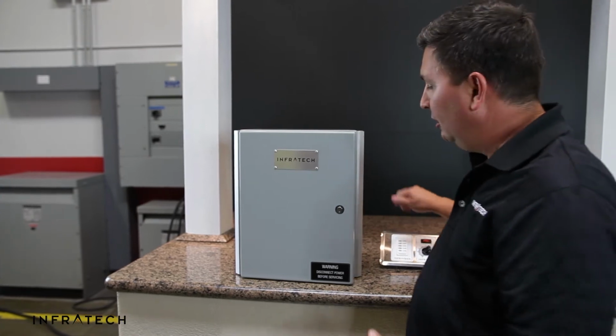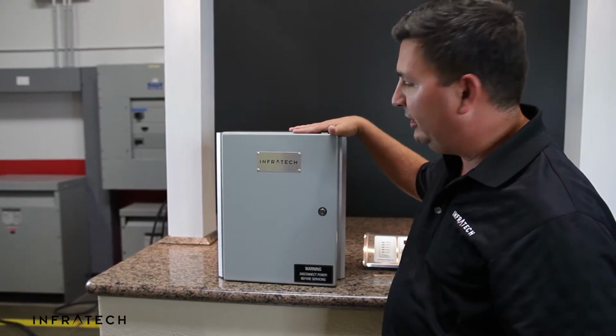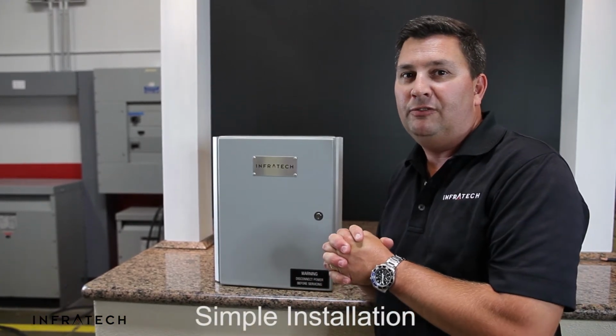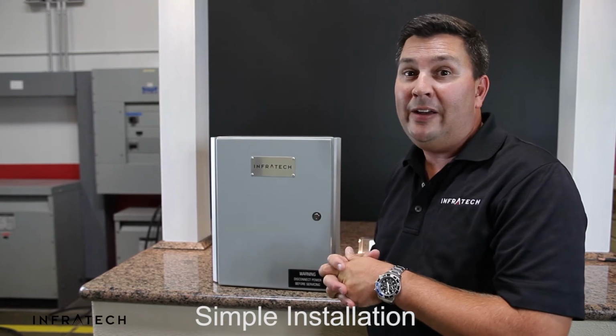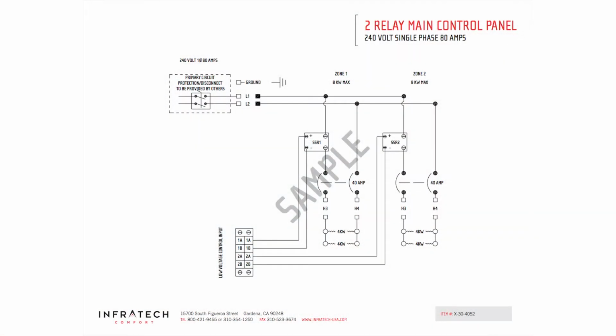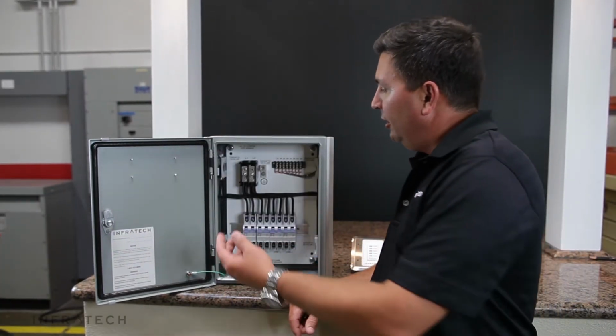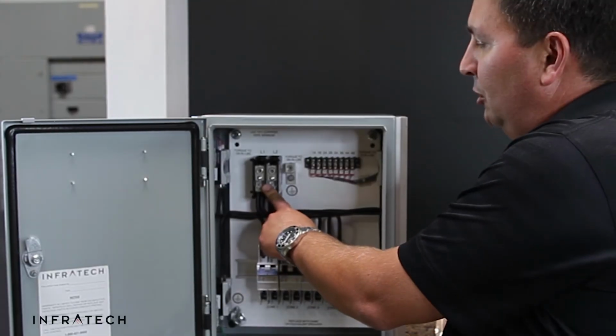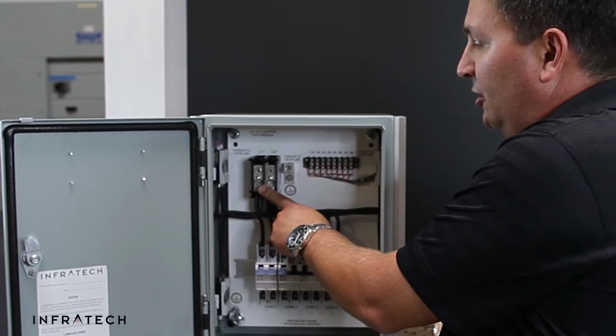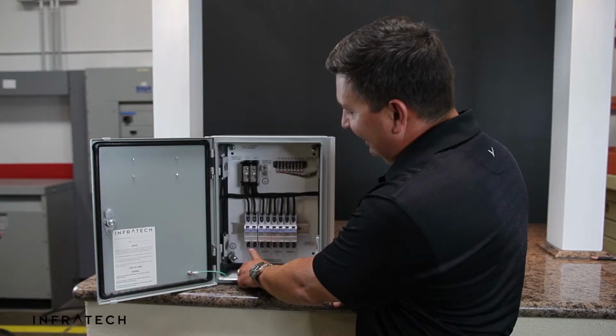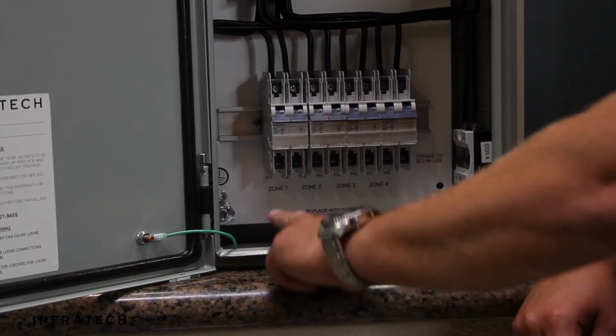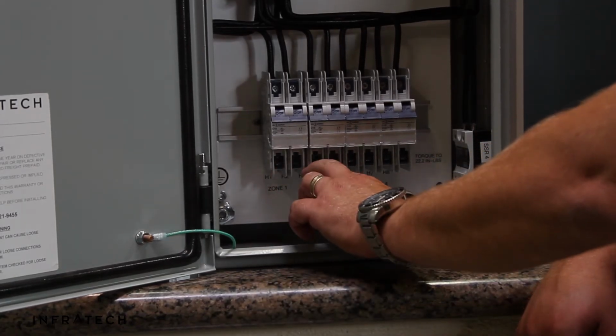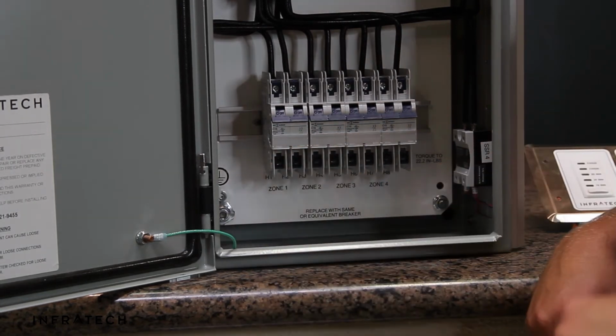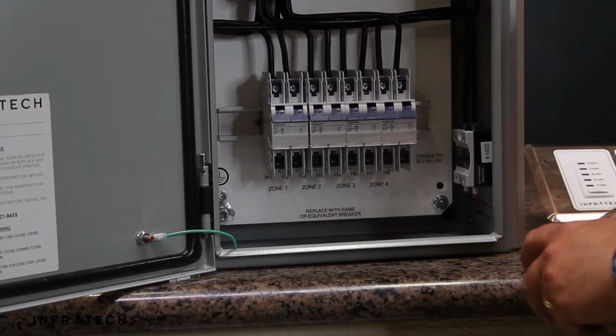Now that we've selected locations for the analog control and the main relay control panel, installation is very simple. You'll need to follow the wiring diagram supplied with your control to get the exact configuration that you've ordered. Most controls are configured in a similar fashion where you will bring the main feed to the main distribution block, however many amps specified on your drawing. You'll then connect the heaters to the circuit breakers. It will show you H1, H2, H3, H4, and connect the appropriate heaters to the breakers as specified.